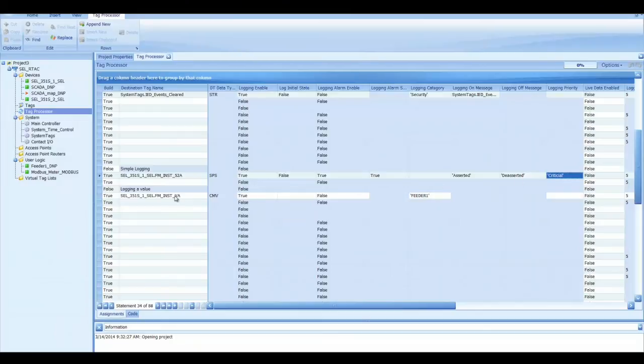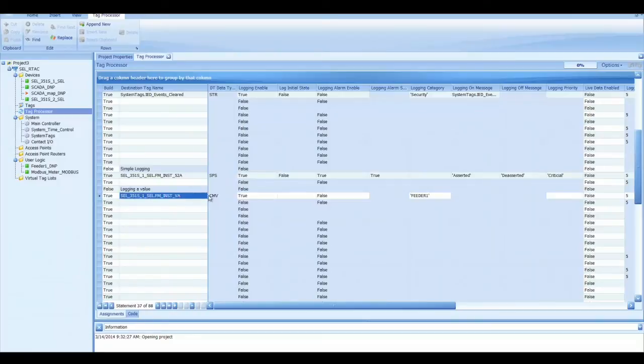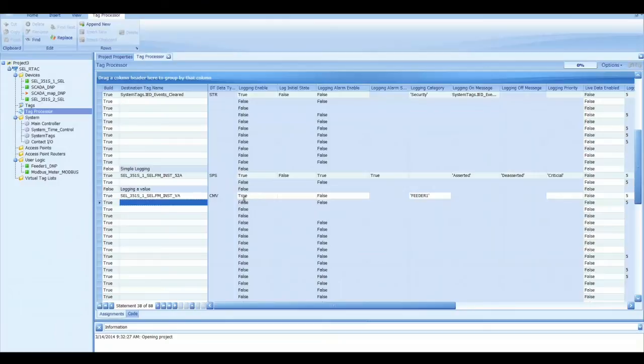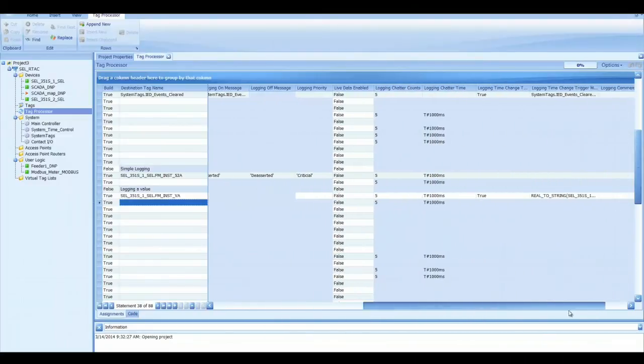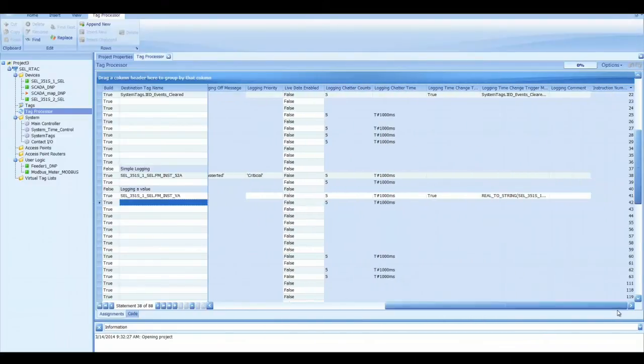The next thing I want to do is log a value. So in this circumstance I have an analog value which happens to be a complex measured value. I put that in the destination tag name. I set logging enable to true. The logging alarm is false because I don't really care about putting it in the alarm. The category I'm going to put is feeder1. And then the next thing I'm going to do is a little bit differently. I'm not going to log it when the value changes. I'm going to log it when the time changes.